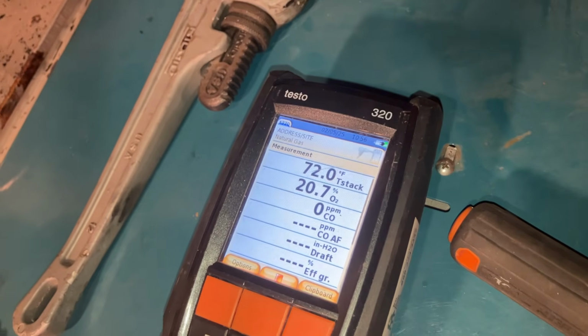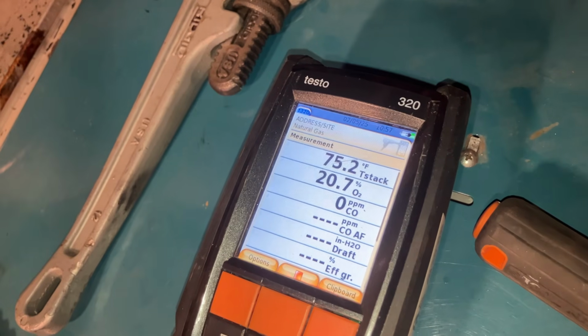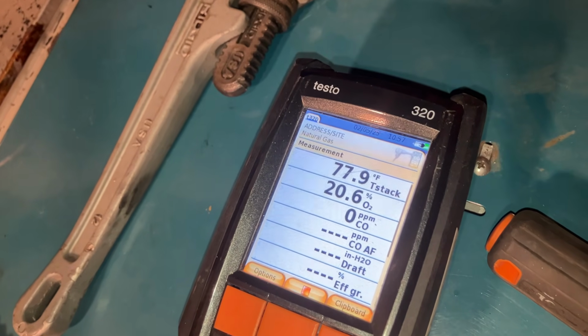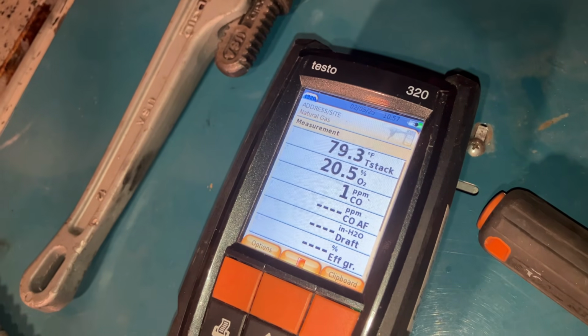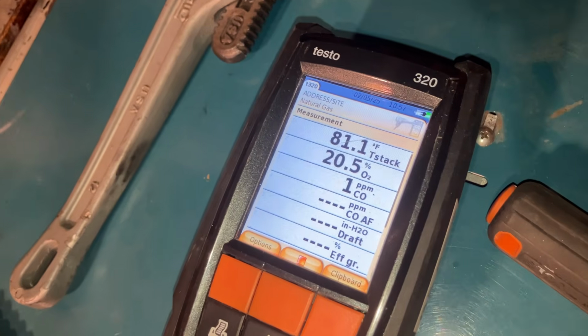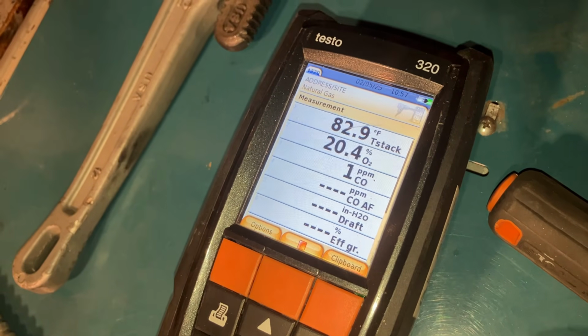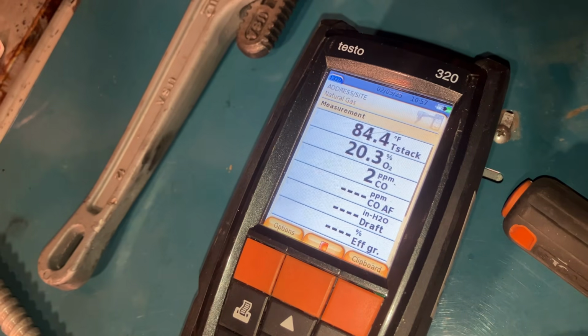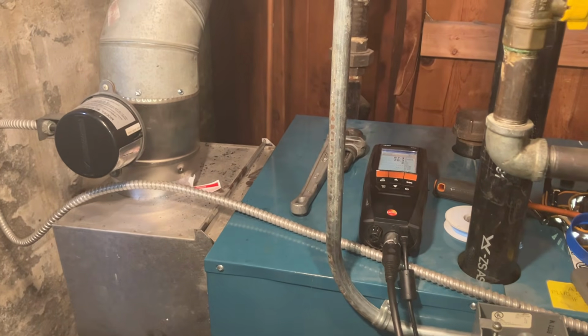Been there, done that. All right, let me show you where this probe is going to go. We need to be inside the top of the boiler, okay? Before it starts getting diluted with air. All right, boiler's off. We have a little bit of heat coming from that pilot burner. 77, 78 degrees. Probably going to be closer to 85 or 90 by the time that's done settling. But look at that already. We have 1 part per million of carbon monoxide. 2. Fascinating. 85 degrees inside the top of that boiler. That is fascinating.